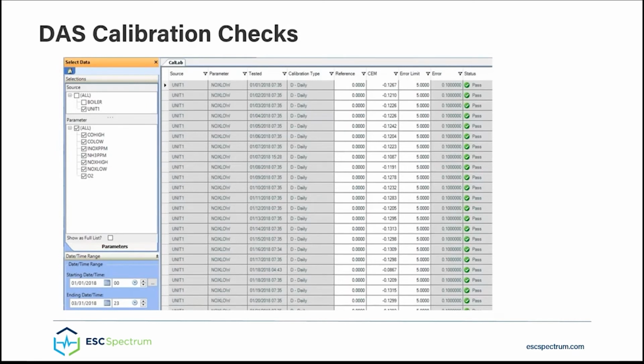Your DAS should allow you to see the current calibration status of each parameter. It should automatically calculate calibration errors as data changes, and it should allow you to export data directly to Excel.